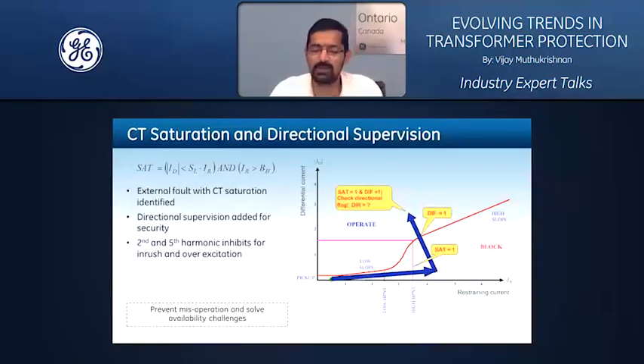And that's what you see here in this particular slide. A technique that is deployed in the 845 can detect: is there a true fault happening in my transformer? Is my CT saturating? If yes, I would like to make my relay secure with a directional supervision functionality. This essentially prevents misoperation for a through fault and ensures that you don't lose availability of your asset through a sudden shutdown of the transformer that affects your system. Those types of problems do not happen when you have solid through fault stability through CT saturation detection and directional supervision.